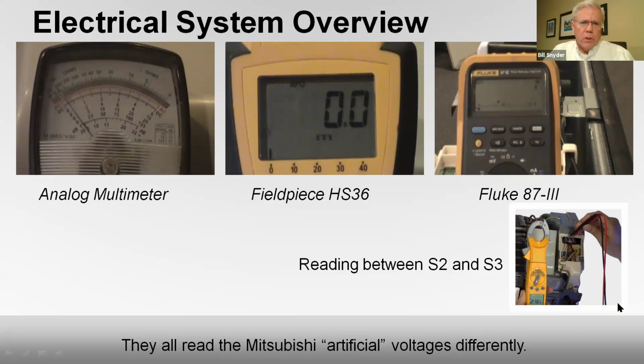I would suggest if you have a meter that's not one of these, to put it on a good system you know is working fine, just to see what you could expect. So if you do have to go out on a piece of equipment that's giving you some problems, you can see if it's acting correctly or not according to the way your meter works.